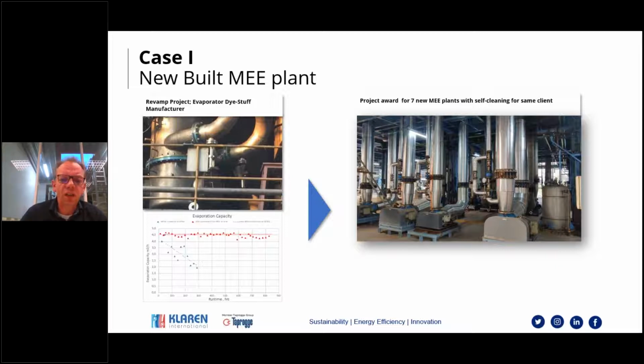So we retrofitted an existing first effect of an evaporator plant with our self-cleaning technology. We did this by installing equipment like the inlet channel, an outlet channel with the particle separator, and a downcomer. In this case we also needed to shift the vapor liquid separator. But after the retrofit, we really had a very positive impact on the evaporation capacity, because that was also the reason why we were approached by the customer. What we saw before is that the evaporation capacity reduced from, let's say, a design capacity of around 4.5, 4.8 cubic meters per hour, to only half in an operating period of 300 hours. So that is around 10, 12 days.